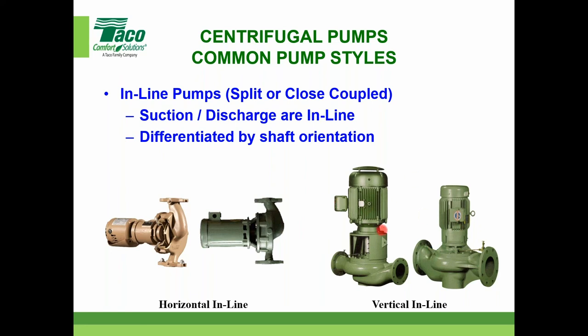for these type of pumps, these two right here especially, is they do not require alignment in the field. They are bolted and they are in alignment prior to, they're not like a base mounted pump that has to be technically probably laser aligned. And it's probably in some of your specifications that's the requirement to guarantee the proper alignment. But nonetheless, these don't require alignment, and that could be a big deal if you've ever had some noise or vibration issues or whatnot. Just something to consider there.